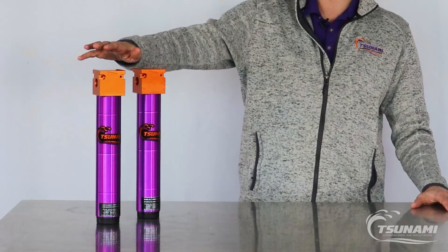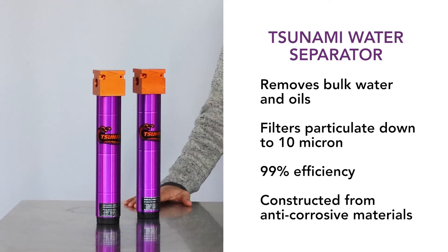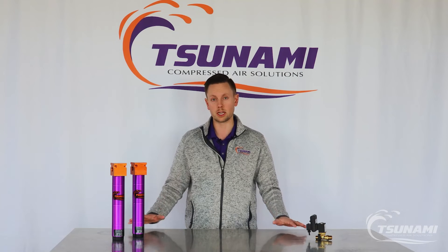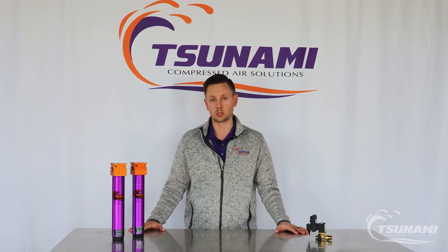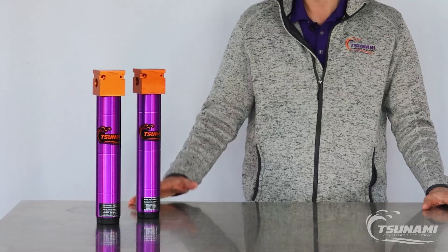To my right here is a water separator. Water separators are specifically designed to remove bulk liquids as well as oils and particulate down to 10 micron. Crucial for any air system to make sure you're not getting water or oil in your lines, but in addition to that, any large particulate that might impinge or damage equipment.